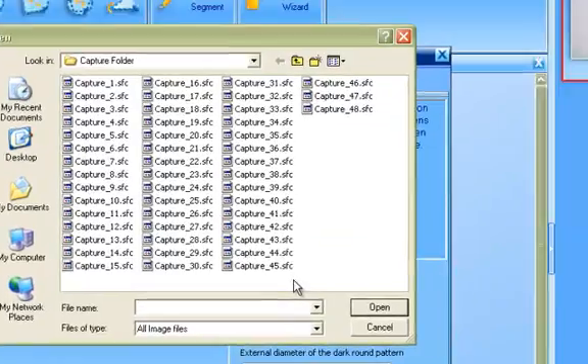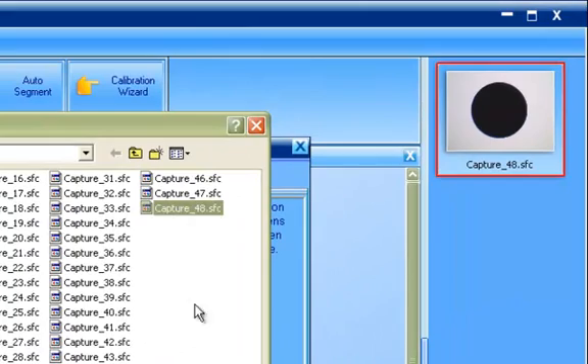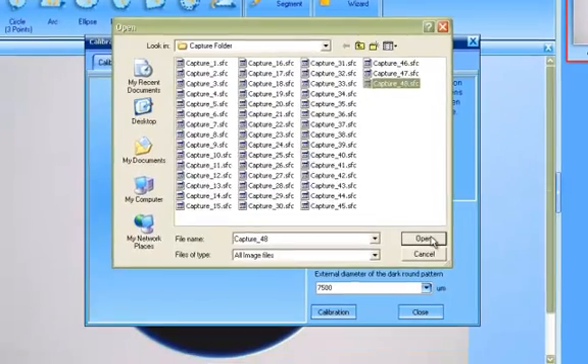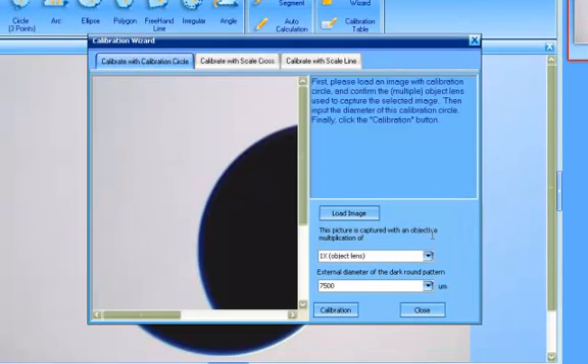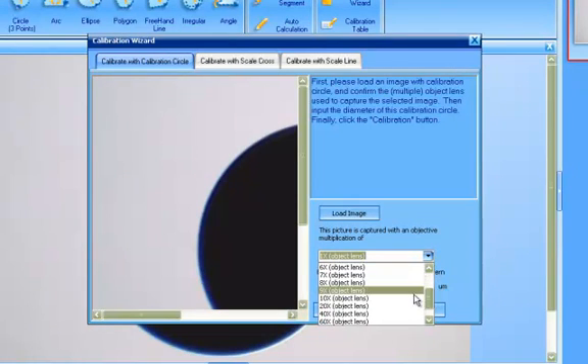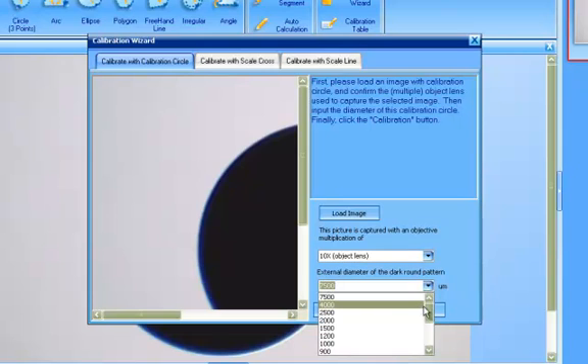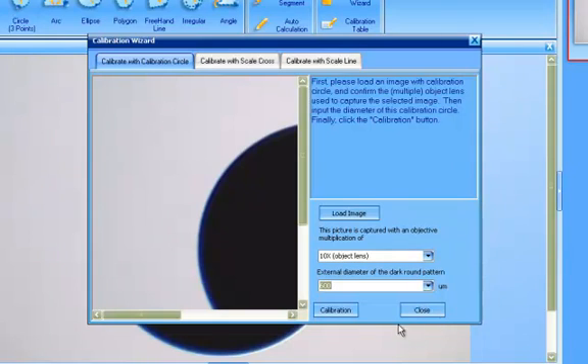So first load the image that we've just captured which is capture 48. Then select the objective that you've used to capture the image. In our case we've used a 10x objective. And let the computer know how big the circle is. You can read that on the calibration slide. In this case it's 600 micron.